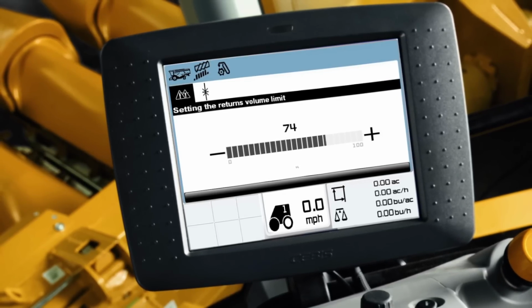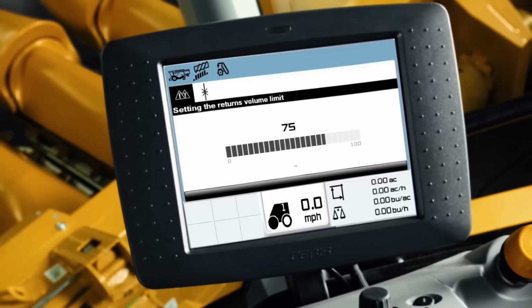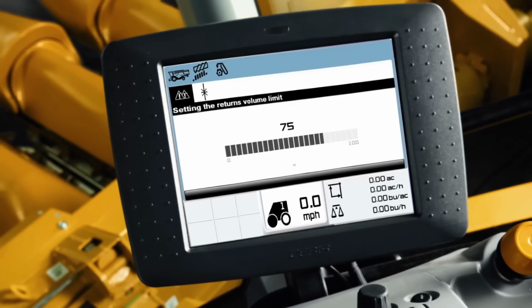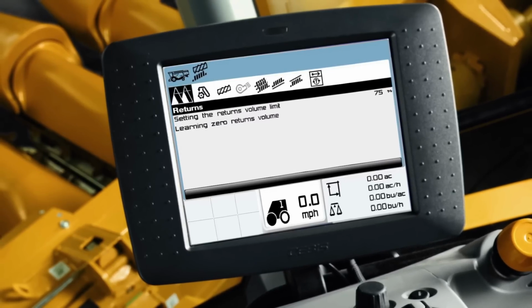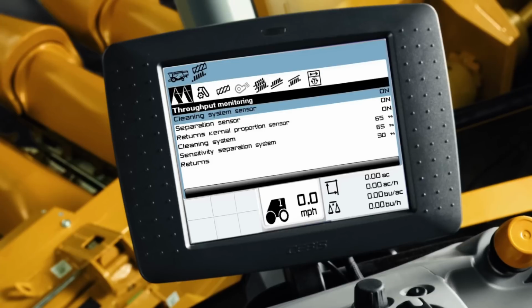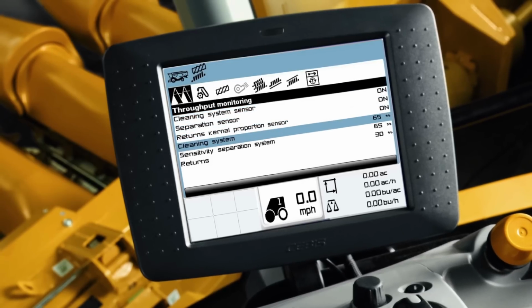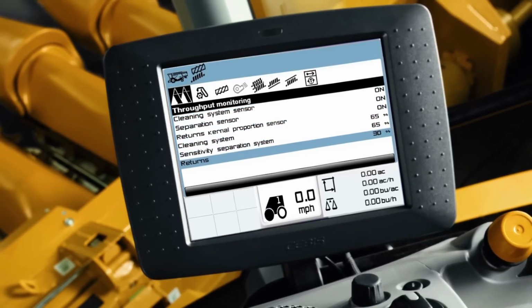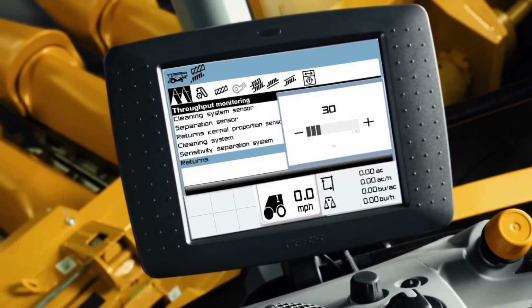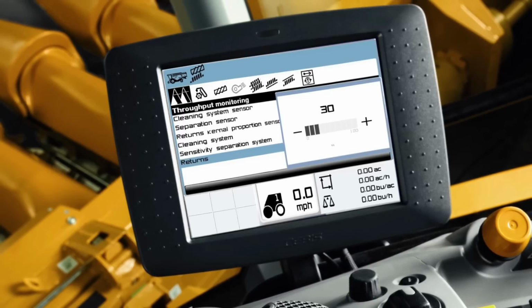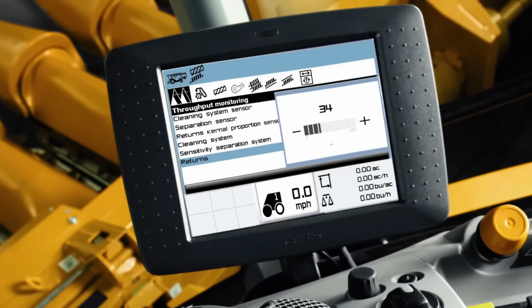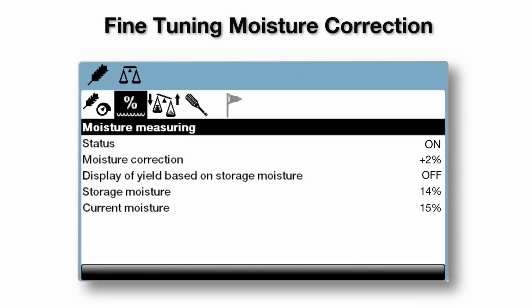A higher number means more returns will be allowed. A lower number means fewer returns will be allowed. To finish calibrating your returns volume, select Throughput Monitoring and choose Returns. Likewise, a higher number tells CEMOS to allow fewer kernels in returns, while a lower number tells CEMOS to allow more kernels in returns. Next, we're going to fine-tune the moisture correction.